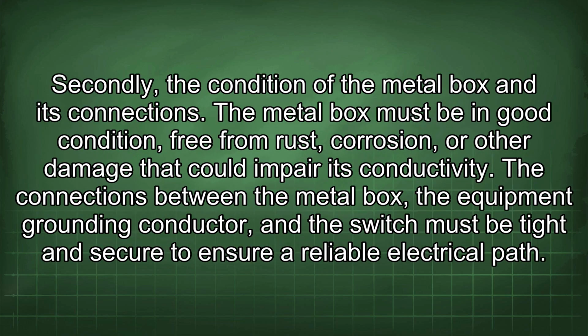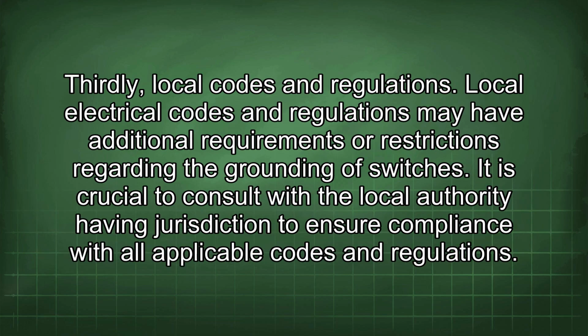Secondly, the condition of the metal box and its connections. The metal box must be in good condition, free from rust, corrosion, or other damage that could impair its conductivity. The connections between the metal box, the equipment grounding conductor, and the switch must be tight and secure to ensure a reliable electrical path. Thirdly, local codes and regulations. Local electrical codes and regulations may have additional requirements or restrictions regarding the grounding of switches. It is crucial to consult with the local authority having jurisdiction to ensure compliance with all applicable codes and regulations.